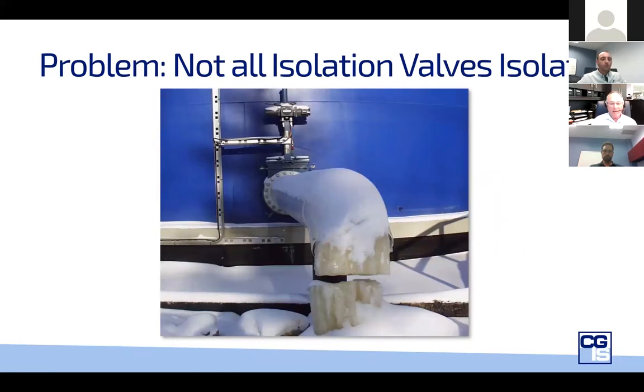This picture is a really good one because everyone can see that something is happening downstream of the isolation valve and it's not good. This valve is in northern Canada where the ambient temperature for seven months of the year is below zero. That whitish object inside the pipe — that's water. It came from inside the tank. The duty of that valve is to drain the tank. The allowable leakage rate of that valve was such that it allowed the water to come out, freeze, and make an iceberg.